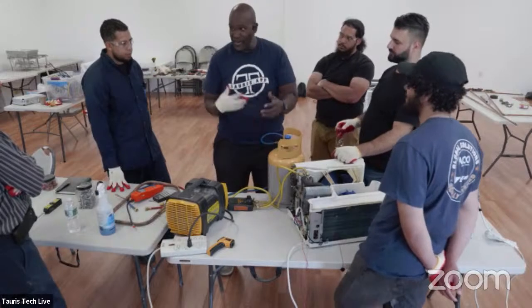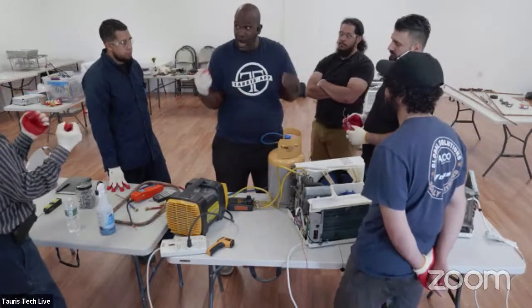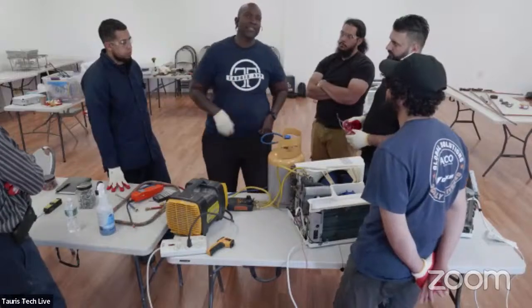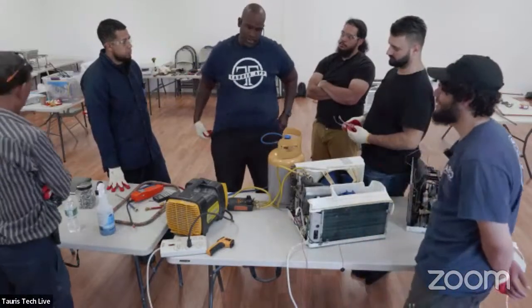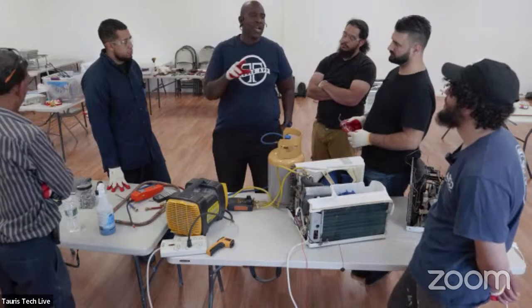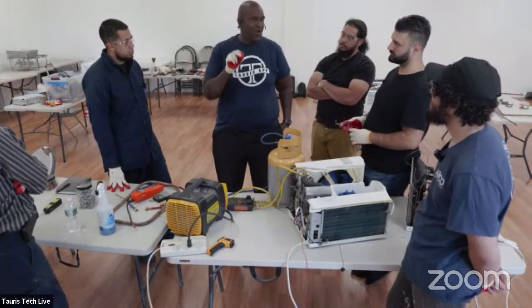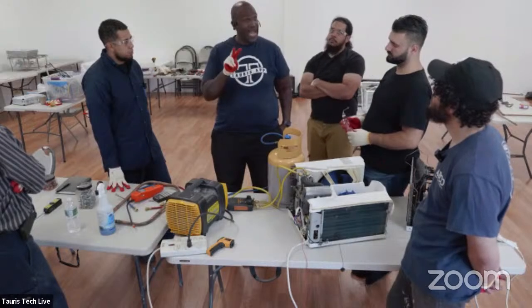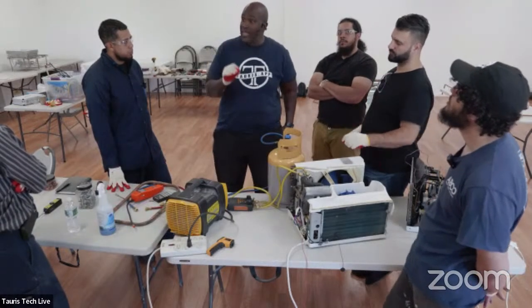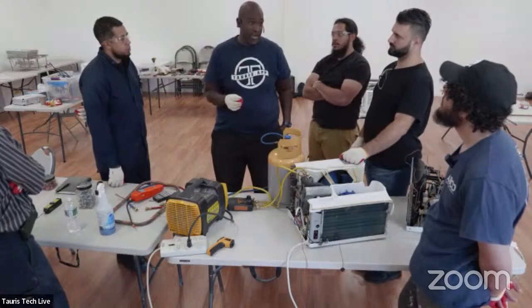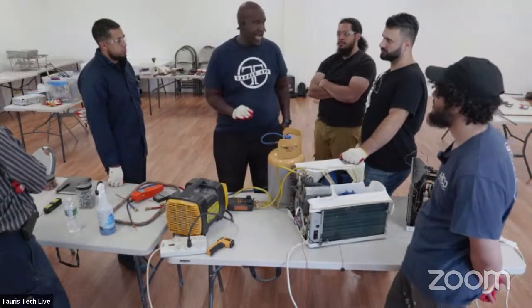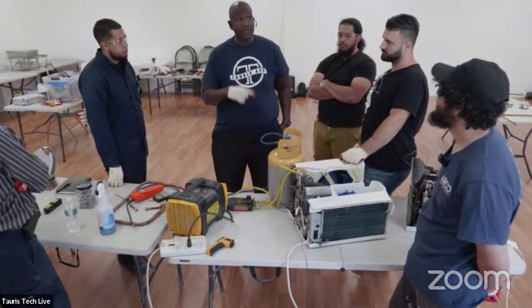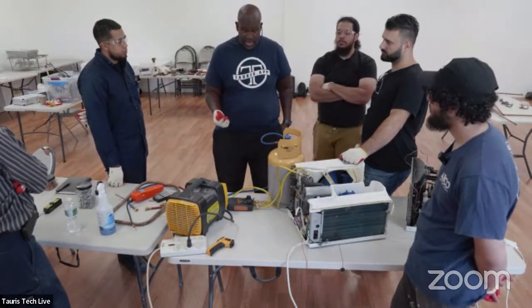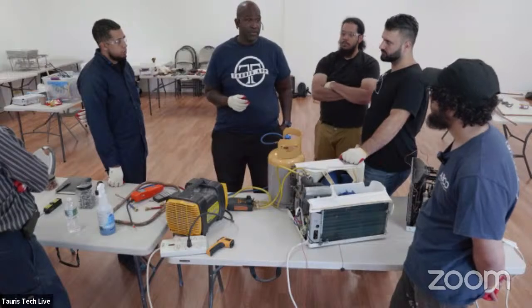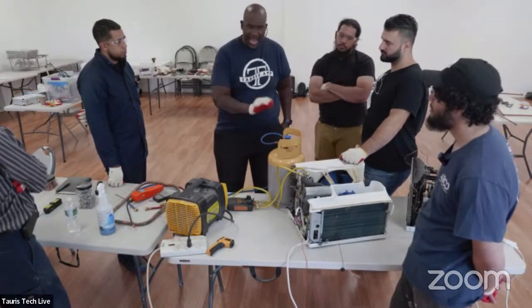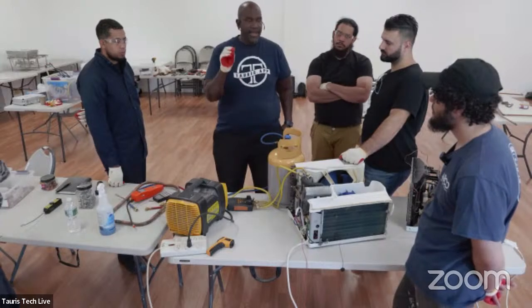Because when you're doing this stuff, when you're working on a machine that has hundreds - guys, I was at Rockefeller Center, their recovery tanks held 19,000 pounds of refrigerant, and they had two. So you're talking about 40,000 pounds of refrigerant, and the procedures are exactly the same. As a matter of fact, the school we went to - next time we go, we're taking gauges, we're putting gauges on those machines. But it's exactly the same. You have to understand how this stuff works.